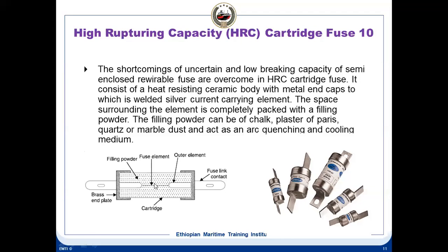So if you use a very low voltage, this gap is much lesser. If you use higher voltage, the gap is more. So the arc cannot build up. That's the difference between the low voltage and the significance of the voltage ratings. So voltage rating has to be higher so that there should be enough gap. And so it protects your equipment in case of a short circuit, basically from the arc.